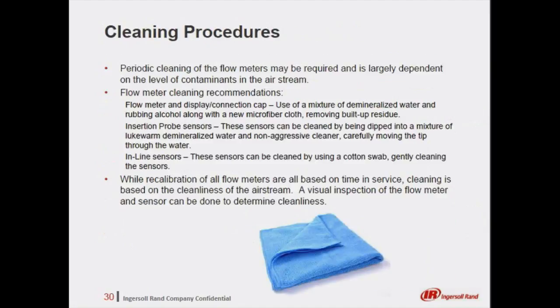Transitioning over to consideration for flow meters that have been installed for a period of time, cleaning of the sensors may be required and is largely dependent on the level of contaminants in the airstream. It is recommended to clean the flow meter probe and display connector cap with a mixture of demineralized water and rubbing alcohol along with a new microfiber cloth, removing built-up residue.